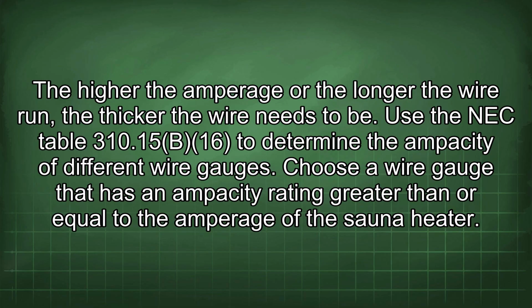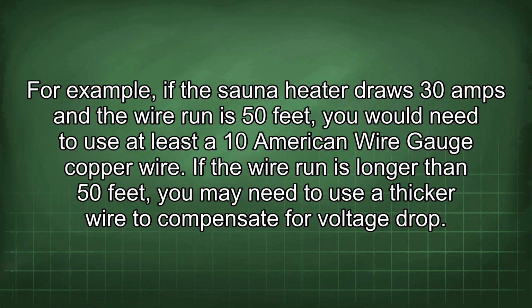Use the NEC table 310.15(B)(16) to determine the ampacity of different wire gauges. Choose a wire gauge that has an ampacity rating greater than or equal to the amperage of the sauna heater. For example, if the sauna heater draws 30 amps and the wire run is 50 feet, you would need to use at least a 10 American wire gauge copper wire.